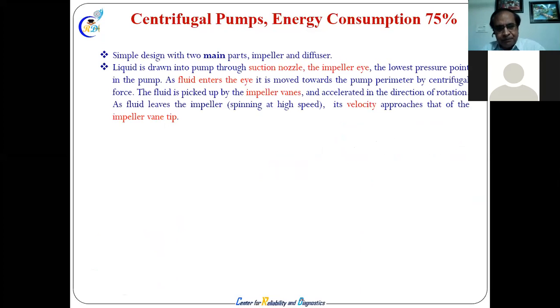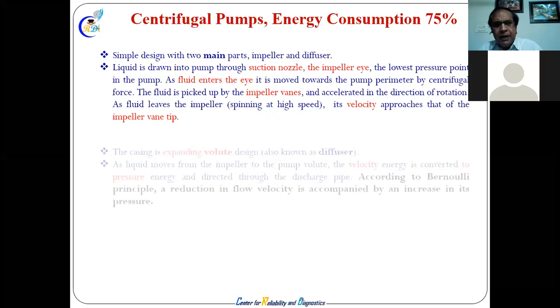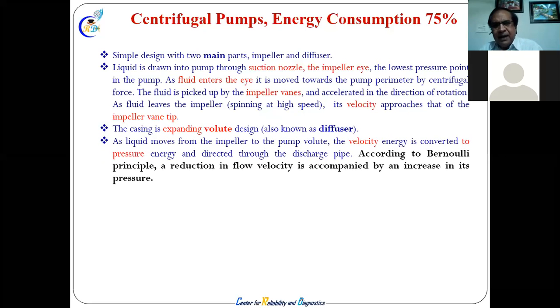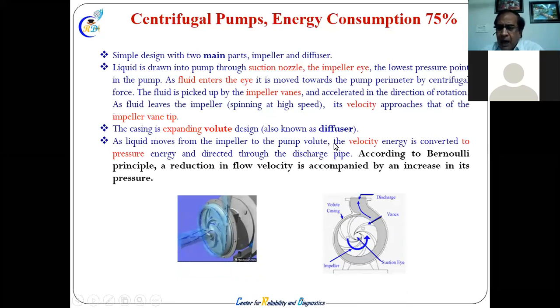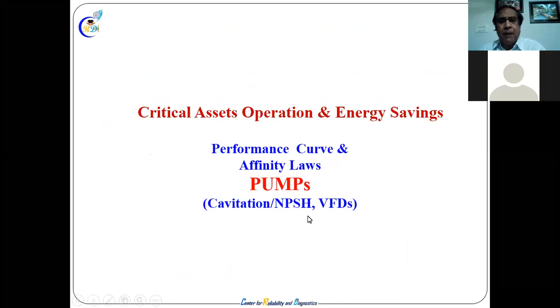Okay, so in a centrifugal pump, how does it work? Impeller eye, water is coming into the impeller at low pressure, and you get more pressure while pulling out of the pump. The impeller vanes accelerate the fluid, and you get higher velocity, and in the diffuser section of the pump we get more pressure. That is the way in the volute, also called the diffuser. Okay, so this is how the centrifugal pump works, and this is the volute casing. And the increasing area, or increasing volume, you can say, is towards the discharge, as the impeller is moving. So this is the centrifugal pump in a nutshell.